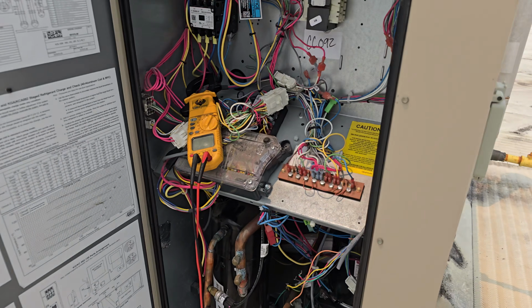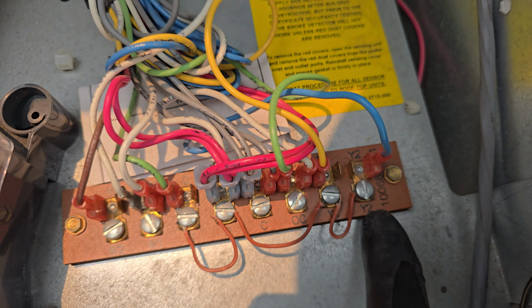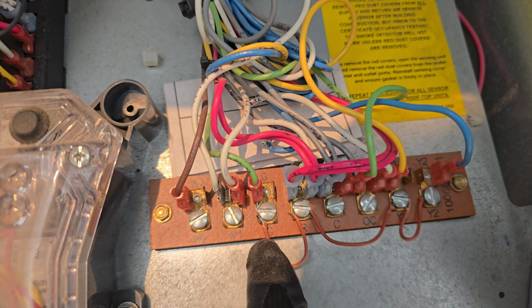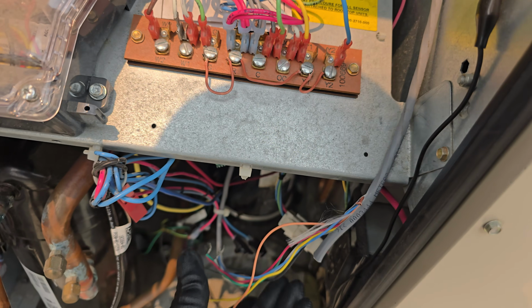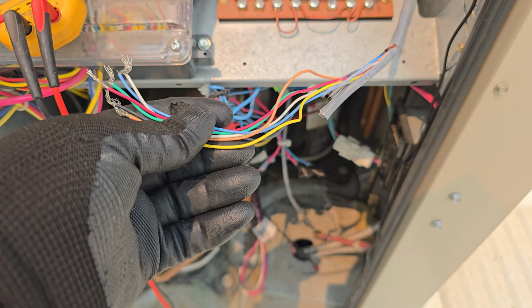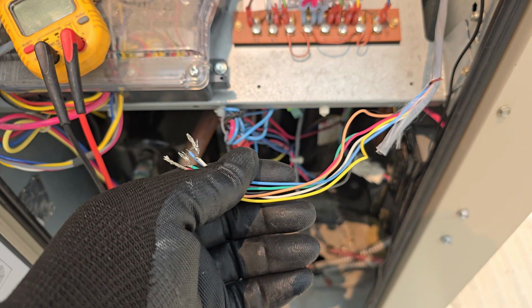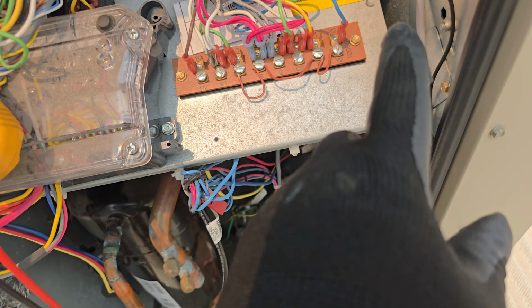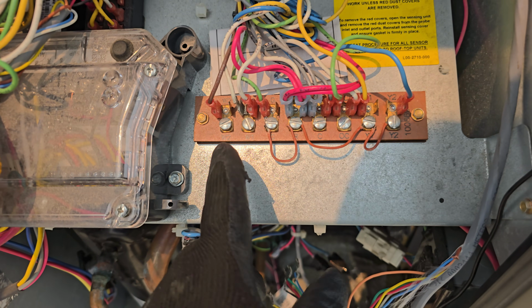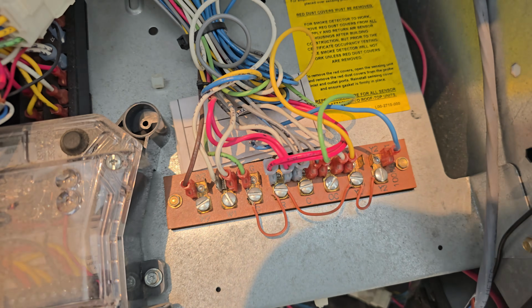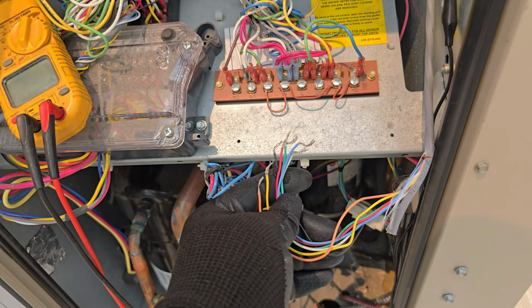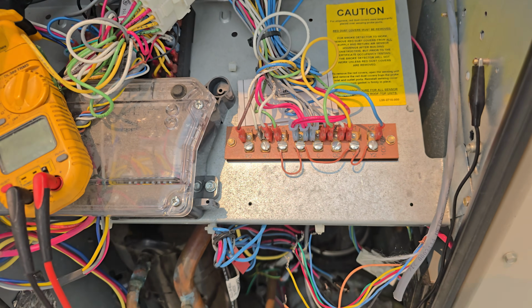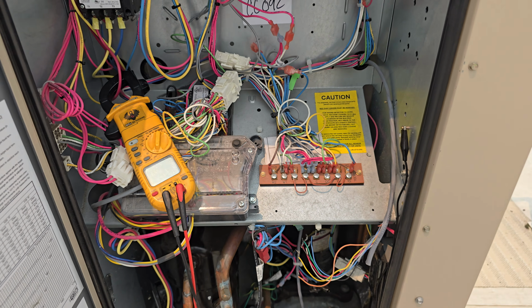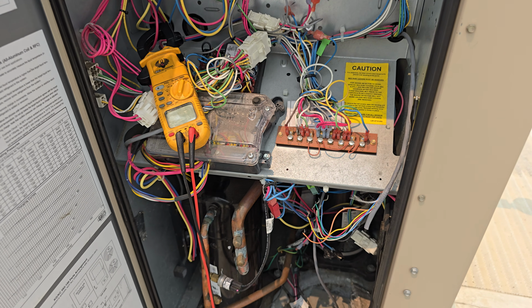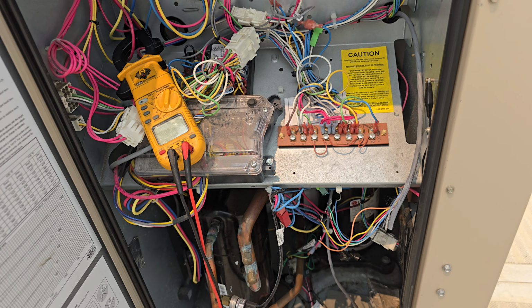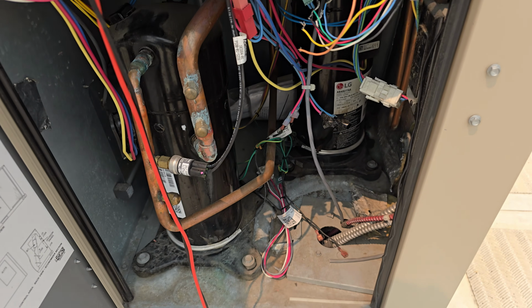Okay, so what I did here was put a jumper between my Y1, Y2, my R and my G, and I have isolated the low voltage wiring, which is the thermostat wire. Before I took this out, I took a picture. I recommend you take a picture, so when you are putting it back, it will be easier to connect. So I took a picture so I can easily come back and know where they are all going. Now that I've done that, I'm going to turn it on. What I'm doing here is isolation. I want to eliminate the problem if it is coming from the thermostat.